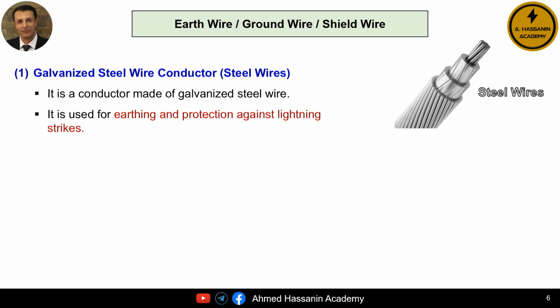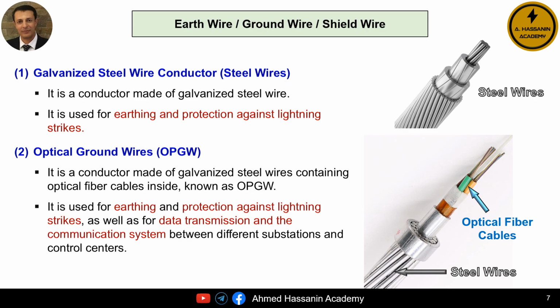But we must know that there are two types of earth wires or earth conductors used in overhead transmission lines. The first type is the traditional type, which consists of a conductor or wires made of galvanized steel. As we mentioned before, its primary function is to protect the transmission line and the insulators from lightning strikes. The second type consists of a conductor or wires made of galvanized steel with an optical fiber cable inside, known as the optical ground wire, OPGW.